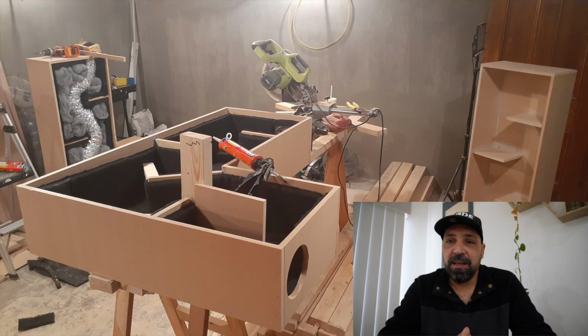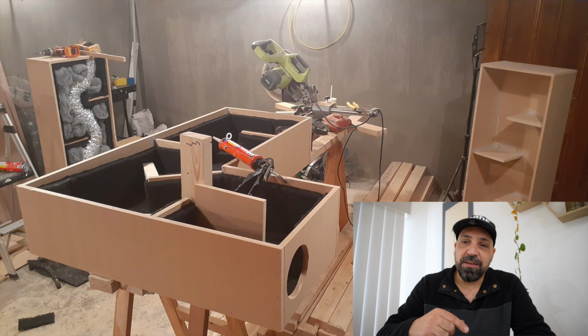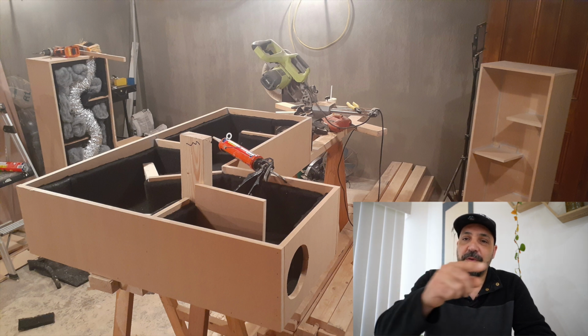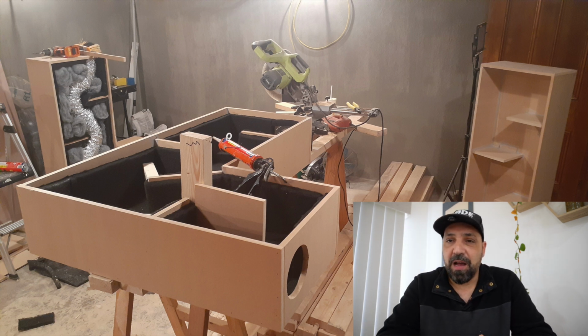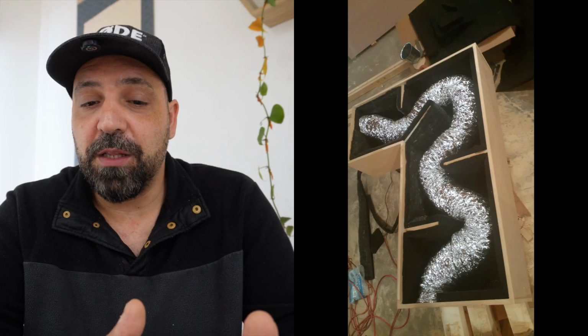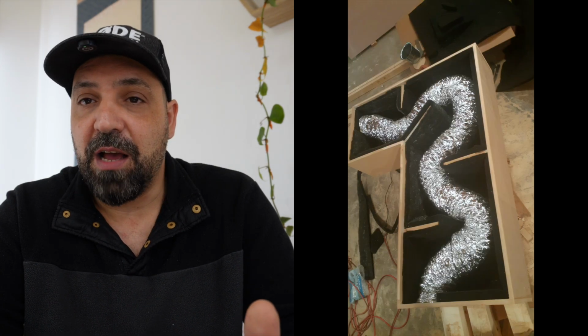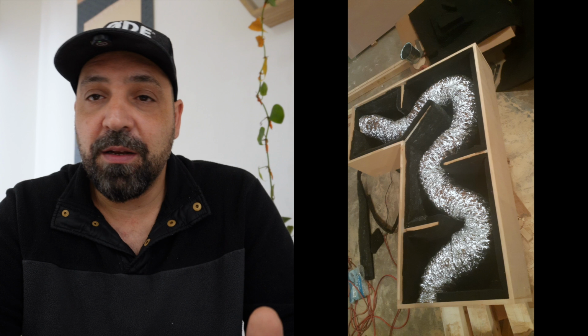We also had these things called sound mazes. As you can see, it directs the airflow down through the ductwork through a series of bends. What happens here is, as the sound energy passes through these obstacles, it loses energy and sound pressure, which helps reduce the transfer of sound. These are filled with polyester sound insulation - we've made three in total at this point.